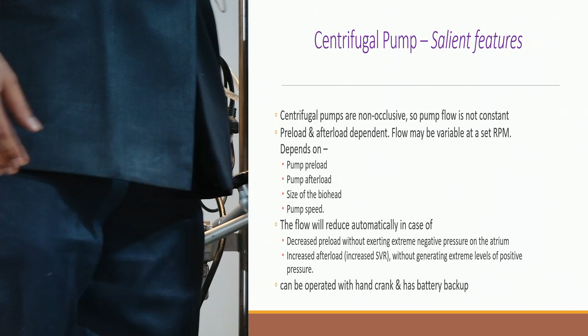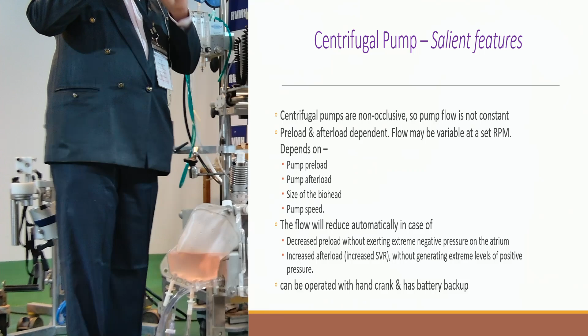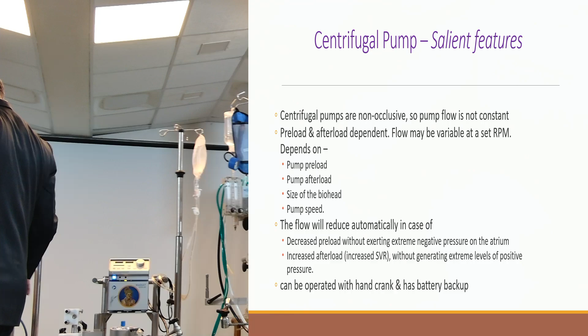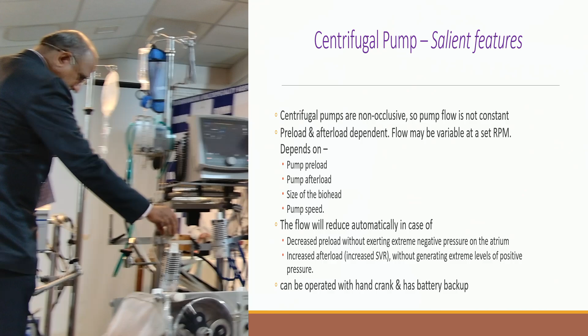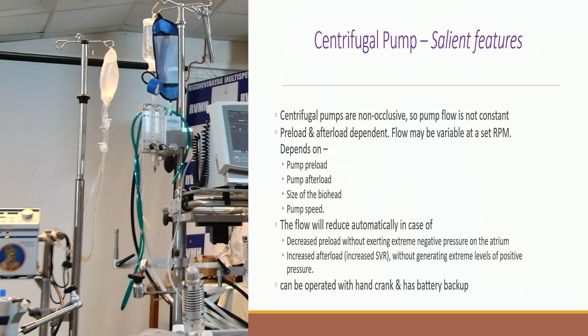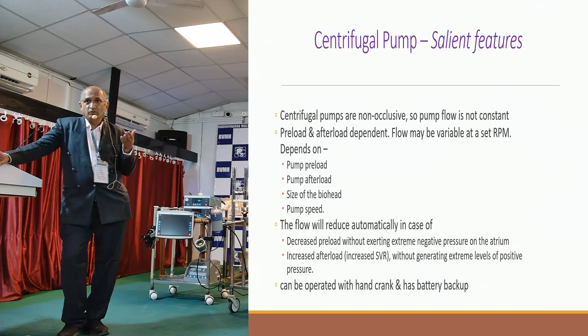This is the Medos pump. Can you see the Medos pump? The size of the Medos pump. The priming volume for this Medos pump is only 10 to 12 ml, while the priming volume for this is around 80 ml. So you can see the different sizes of the pumps. And that's why, as I told you, as the pump size decreases, the RPM requirement will be more to move the blood, because the pump size is very small.